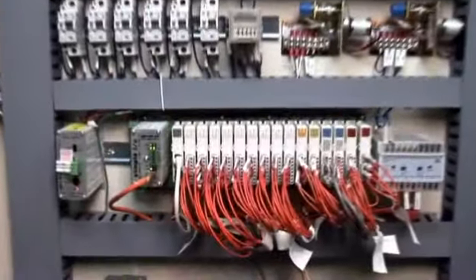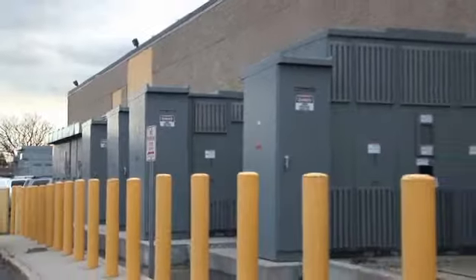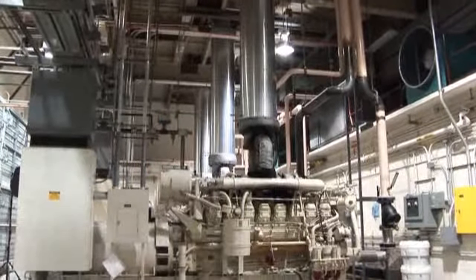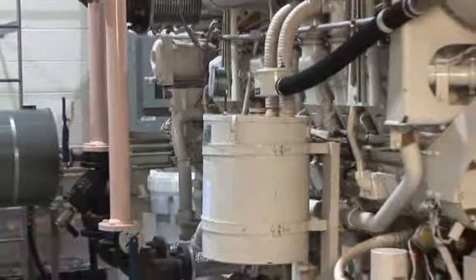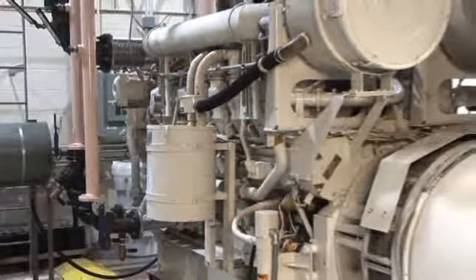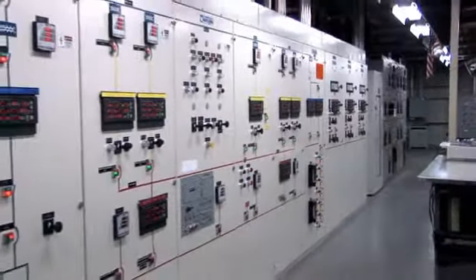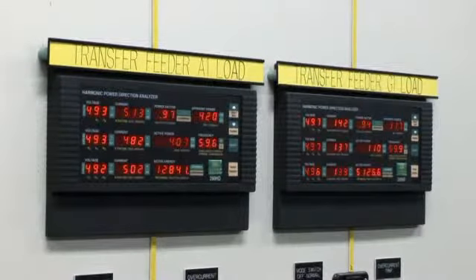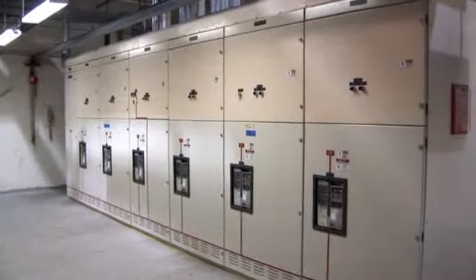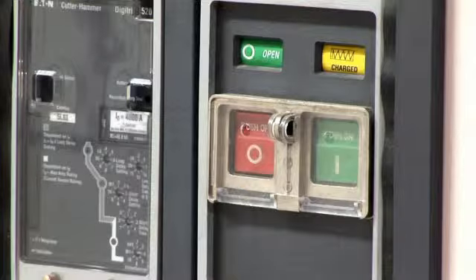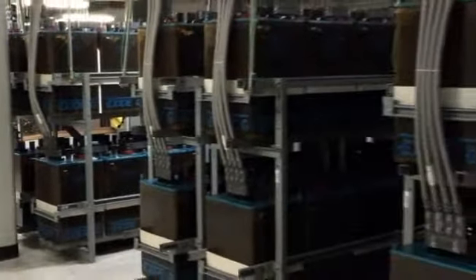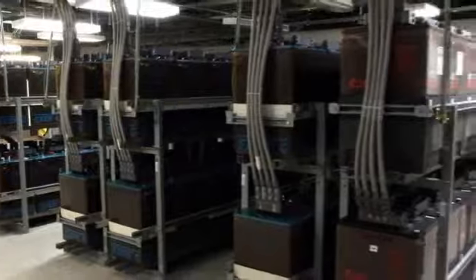We're a systems integrator. We monitor large-scale, high-reliability power systems. We're using the Opto 22 SNAP I/O series product line, primarily with PAC R2 brains. We interface it to everything affecting the power, starting with monitoring the utility power that comes into the building, the generator power that's produced by the generator when it's running. We monitor the fuel tanks. Then we monitor the transition of power, whether the transfer switches are opened or closed, whether the circuit breakers are in the normal position or the emergency position. And then we monitor the health of the battery plants also for the equipment that's providing the actual power to the service generating equipment.